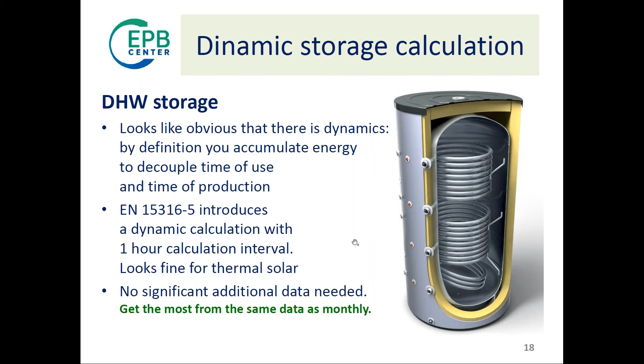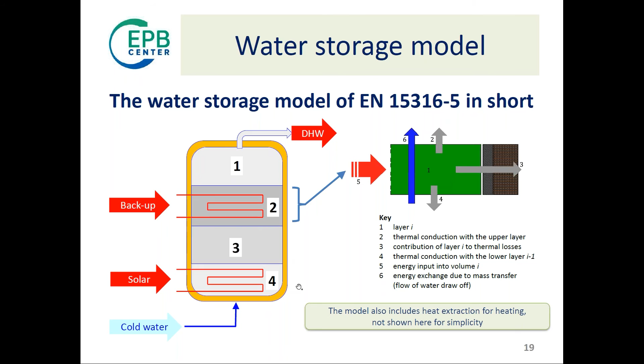We calculate the temperature of the 4 layers in a storage. Typically you have a lower region where you have your solar exchanger, an accumulation area for the solar, a space for the backup heater, and then a reserve of domestic hot water ready to use. You may also take some heat for a heating circuit. The description of all this is just the same as you use for a normal boiler, you just need to know the proportion of the volumes.